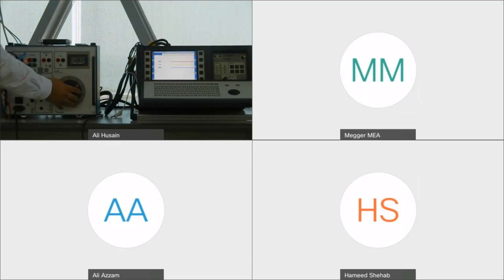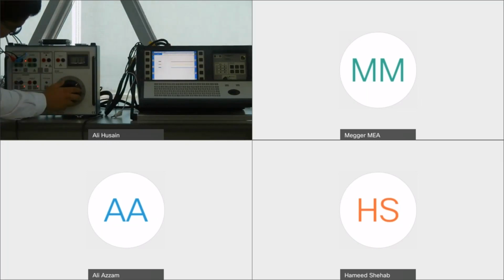And that's the importance of having a variable voltage or power supply. You can decrease the values to do this test. If you are using the DC supplied by the station, this is something you cannot control. That's why this test equipment, or this variable power supply, is required and important.